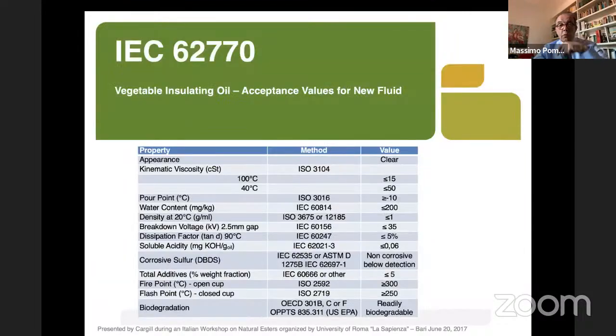We can move on to standards. I'm sure you know IEC, the International Electrotechnical Commission, and this standard has a code: IEC 62770 is the standard giving the main properties for natural ester liquid. We can go through some numbers together, as it reports which properties a natural ester must have before it can be used in electrical transformers.